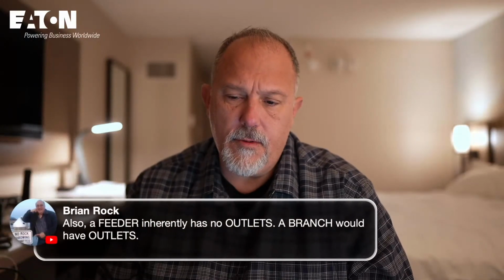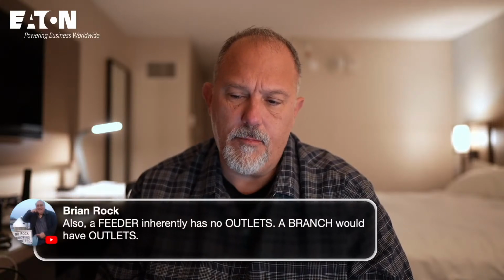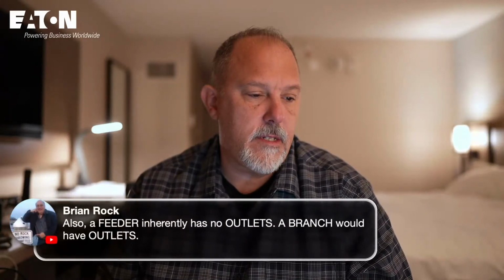What they restructured in B is so they have A as feeders and branch circuits. Now they have B, fire pump circuits. Fire pumps have to use ground fault monitoring in accordance with the following. They have a ground fault monitoring alarm. Also, a feeder inherently has no outlets. A branch would have outlets.